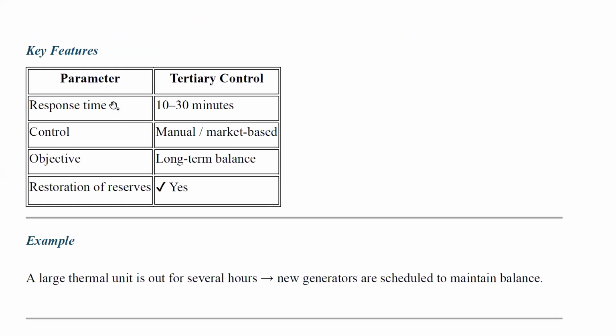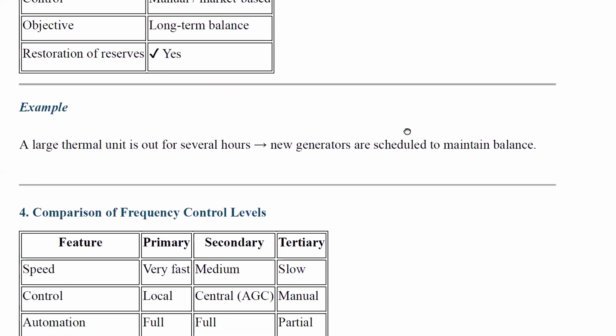What are the key features? For tertiary control, the response time is 10 to 30 minutes. Control is manual or market-based. The objective is long-term balance. Restoration of reserves is yes, so it restores the reserves. For example, a large thermal unit is out of service for several hours, and new generators are scheduled to maintain the balance. So new generators are immediately scheduled. That is called tertiary frequency control.